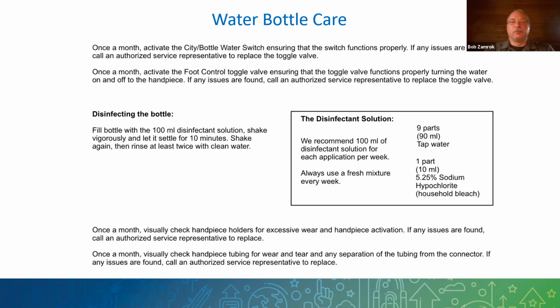Shocking the lines means that you put a high level of disinfectant in there for a short period of time to make sure that you kill any of the bacteria that's growing in there. A solution of 9 parts water to 1 part chlorine is what you could use for something like that, or there are other products on the market that do the same thing. This is the cheapest and most basic way to do it. Chlorine is a great product; all of our water treatment plants use it in our potable water now. But you don't want it to sit in there too long because it can damage your unit, and obviously you don't want that high a concentration going into a patient's mouth either.